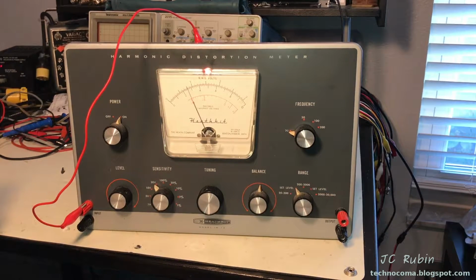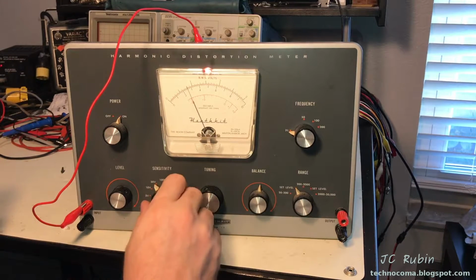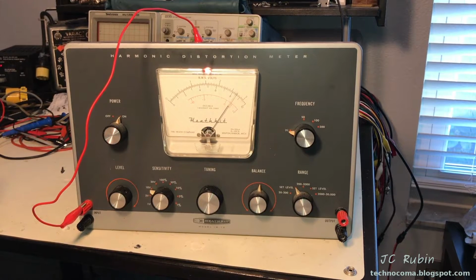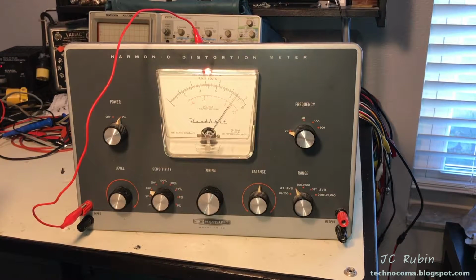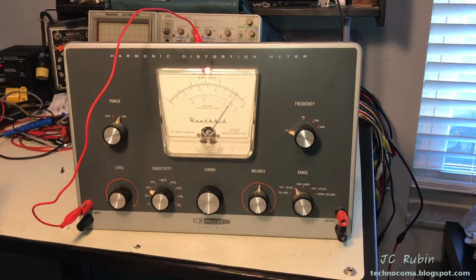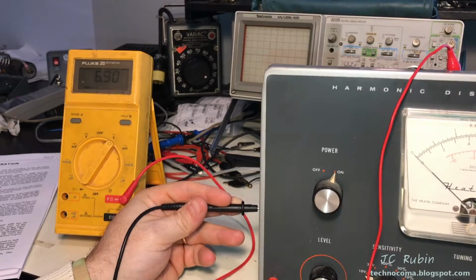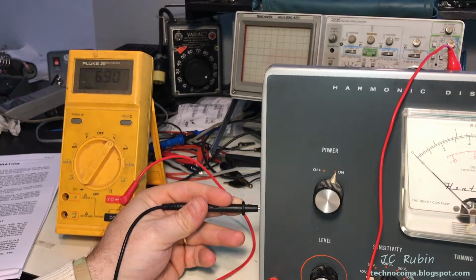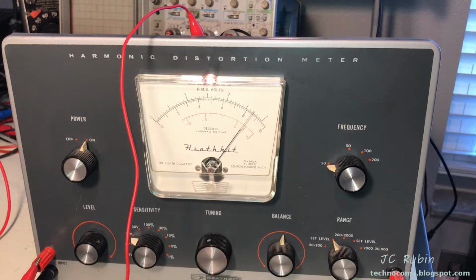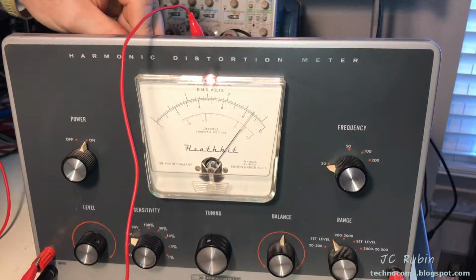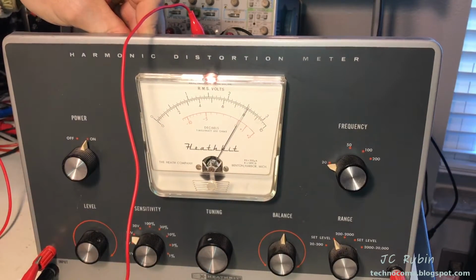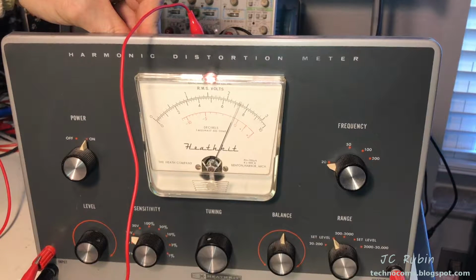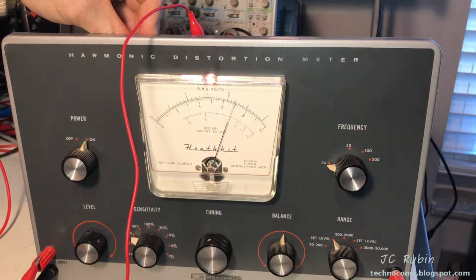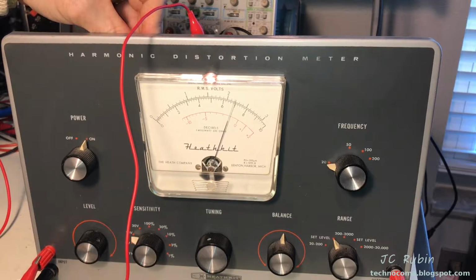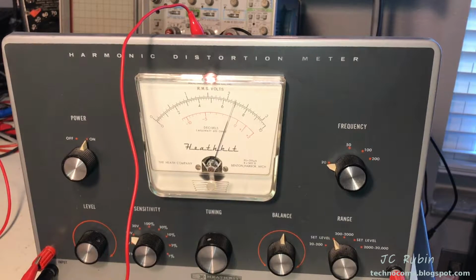Set the sensitivity switch down to 10 volts. I guess the assumption is once you realize that it's less than 10, you're not going to break the meter. We could turn this down to 10 volts, right? Adjust the voltmeter calibration control to show a 6.3 volt reading on the 10 volt scale. Note if a standard meter of known accuracy is available, it may be used to provide a more exact calibration. So I know that with an accurate meter, the pilot is exactly 6.9 volts. So that's what I'm going to be adjusting the meter to. So now we'll get back there. Here we go. There's 7. There's 6.8. There's halfway between 6.8 and 7. There's 6.9 volts. That takes care of the meter calibration setting.